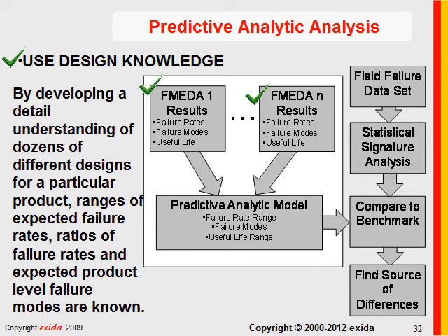We use the specific FMEDA results if we know the specific manufacturer and model number, or we use the generic failure rate results if we do not know the specific manufacturer and model number. And Exida generic failure rate data basically assumes worst of class, so that'll be a higher number.